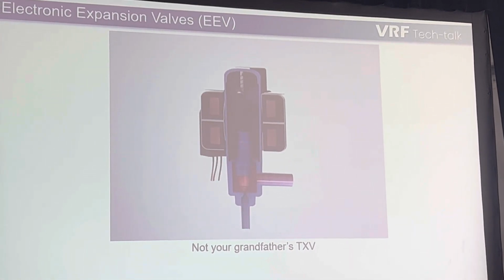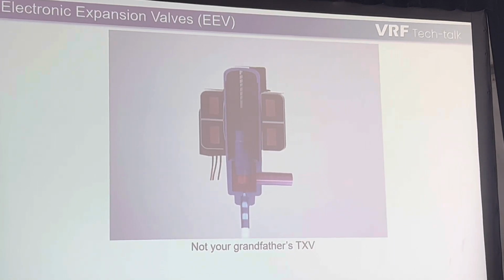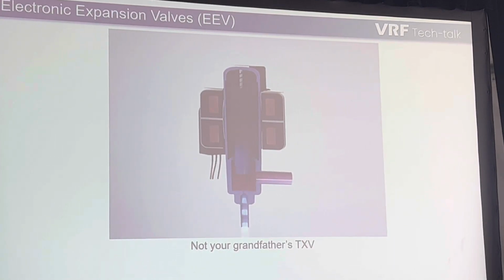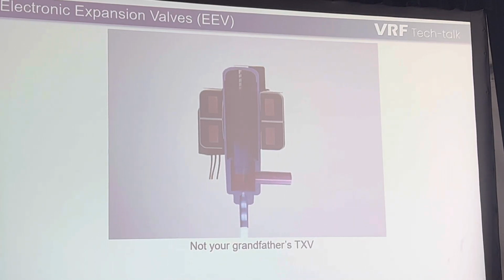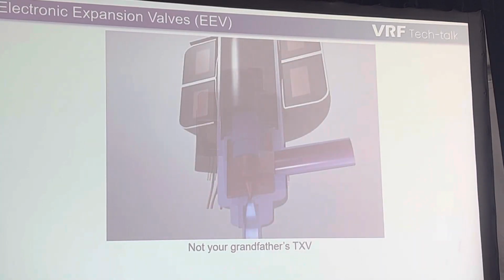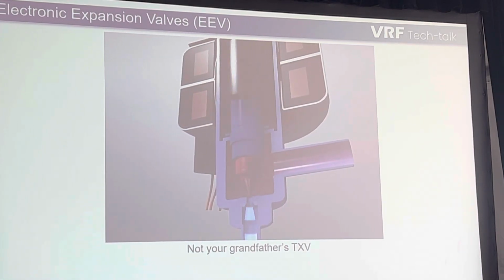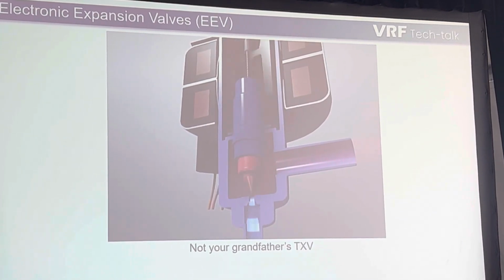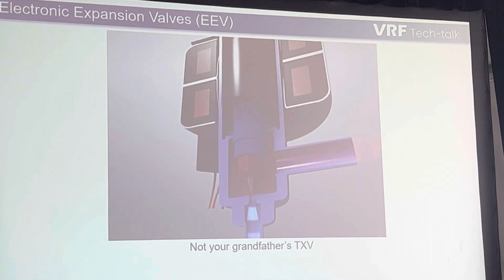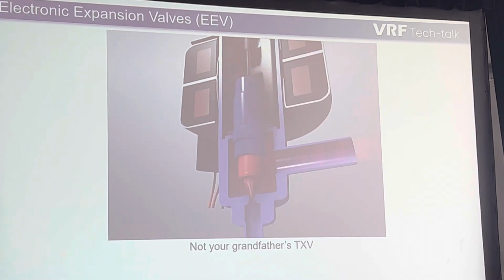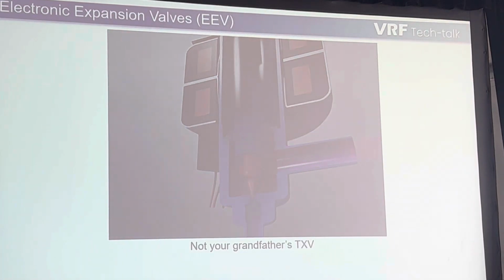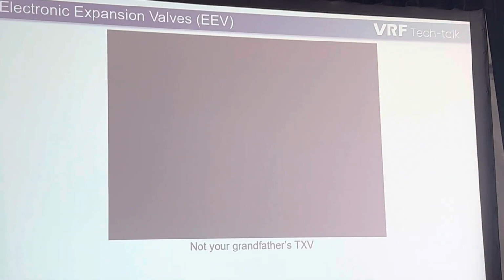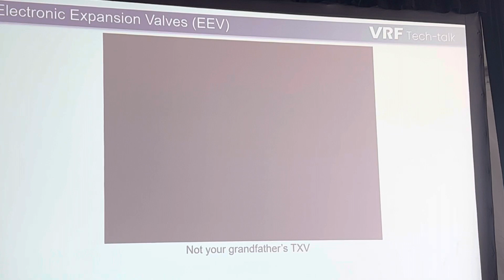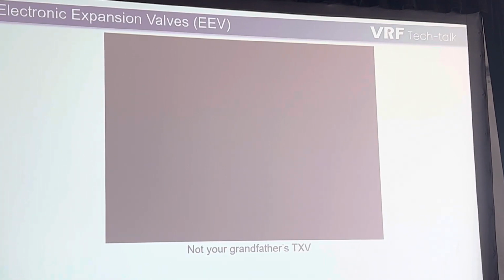But there's also a tool that I've used out in the field that I found extremely helpful, which is the EEV Make tool that can actually allow you to manually drive these using an electronic device in your hand. Now, I tell people to use caution with that. You need to understand how they operate and the valve that you're working on before you use a tool like that, because you don't want to overdrive it or underdrive it and get it stuck somewhere where it's not supposed to be. Right? Every manufacturer drives their valves differently when the unit's turned on and off, how it's power cycled, stuff like that. So we just want to make sure that when you use a tool like that or use any tool like that, you want to ensure that you're following the proper procedures according to that manufacturer. And you're not actually breaking the equipment. All right.